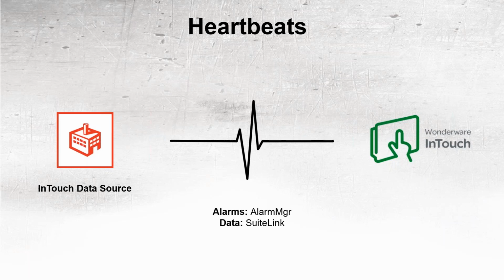So for InTouch, what we have done is we've created a heartbeat feature. You specify a tag, and we're going to write to that tag value 0 through 9. And then we've also introduced a heartbeat suspension feature, which means you tell us a tag to watch for a changing alarm value. It's very similar to a watchdog. If we don't see the changing alarm within the timeout that you set, we know that the Alarm Manager connection has died. And if the SuiteLink connection is still good, we'll go ahead and just pause the heartbeat because the Alarm Manager connection is not good.